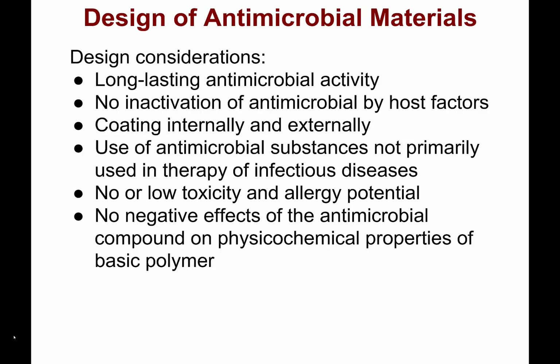When designing antimicrobial materials, there are several considerations. One is that we want to have long-lasting antimicrobial activity. Two, we want no inactivation of the antimicrobial by host factors. So that's inactivation due to the biological response after implantation. If it's a device that has internal and external components and we're going to coat it, we've got to coat both in order to be effective. That pertains to a vascular graft, for example.